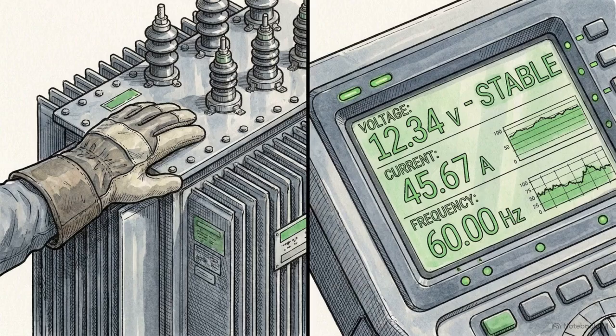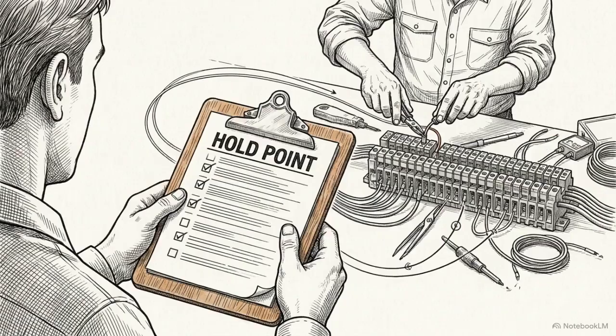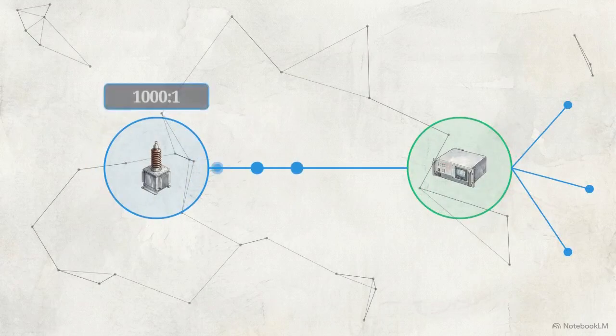During the active AC injection phase, operators physically monitor the unit. They listen for abnormal vibrations or noise from the core, while watching the screen for unstable fluctuations in the measurements. Before the injection sequence can start, a mandatory hold point requires a commissioning witness to physically verify that all burden isolation is complete, preventing any unintended power transfer. Validating the exact step-down ratio is critical.